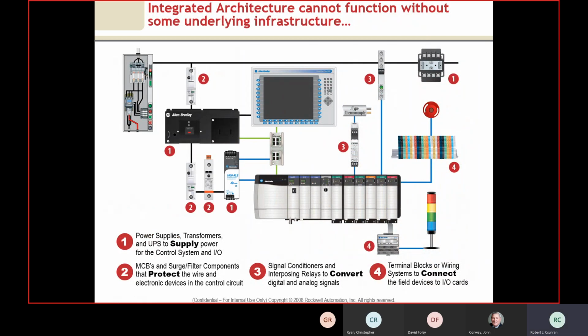So when we look at integrated architecture, we'll notice there are a lot of different things tied together. One of the things we try to do when we look at the control side is break it down into 4 different categories. We've got supply, the supply of power. We've got protection, which could be provided by miniature circuit breakers or surge and filter components. Many times we don't talk about surge and filter, but they can have a huge impact on customers and their systems, and the downtime associated with an overload and damage to the units.